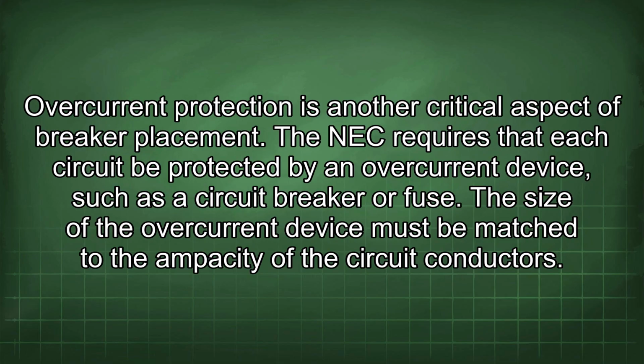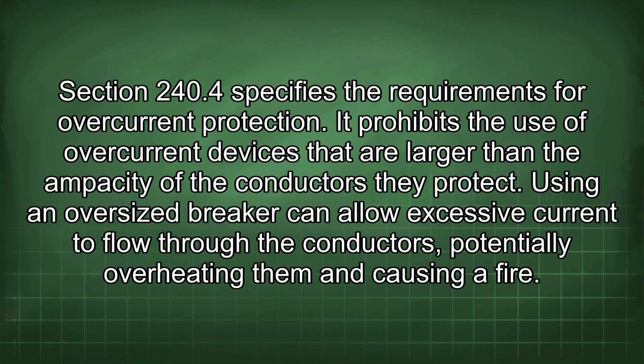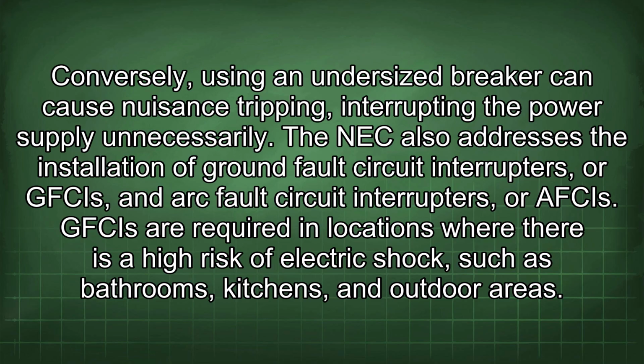Overcurrent protection is another critical aspect of breaker placement. The NEC requires that each circuit be protected by an overcurrent device, such as a circuit breaker or fuse. The size of the overcurrent device must be matched to the ampacity of the circuit conductors. Section 240.4 specifies the requirements for overcurrent protection. It prohibits the use of overcurrent devices that are larger than the ampacity of the conductors they protect. Using an oversized breaker can allow excessive current to flow through the conductors, potentially overheating them and causing a fire. Conversely, using an undersized breaker can cause nuisance tripping, interrupting the power supply unnecessarily.